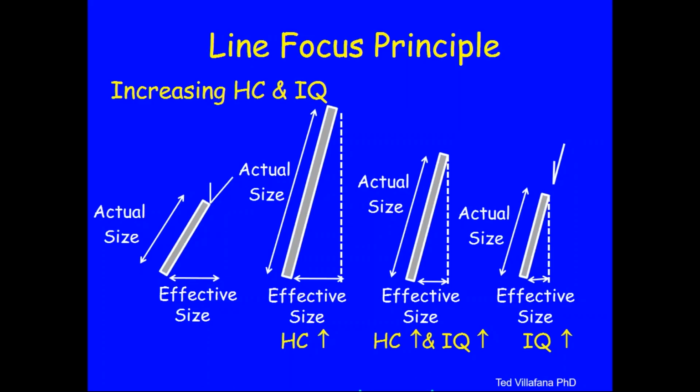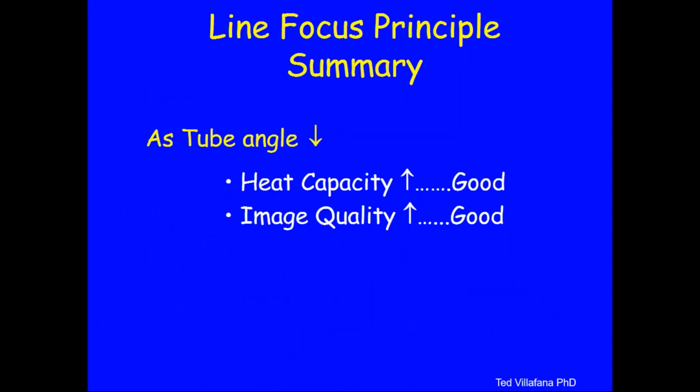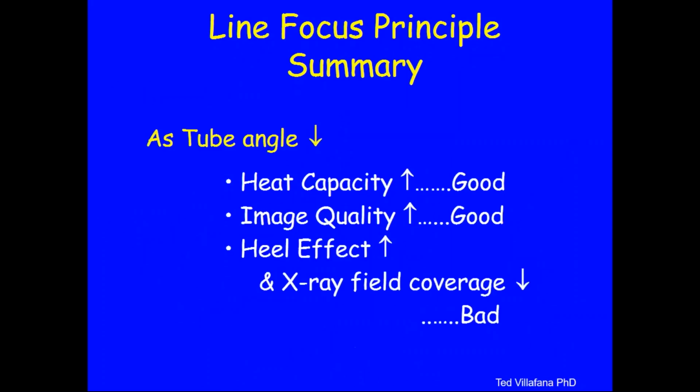Well, there's a limit to how much I can push this, okay? But as seen in these slides, yes, you can cash in on both heat capacity and image quality. Okay? Those are both good. And those are the two statements so far of the line focus principle. But now, the bad. You can only push this so far because then heel effect kicks in.